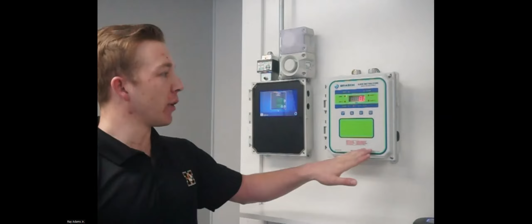Now, the reason that it's a NEMA 3R and not a NEMA 4X is that you do have those internal sensors in there. So there still does have to be air that moves in there in order for you to be able to detect the gas. Whereas our control panel, without any internal sensors, comes standard as a NEMA 4X enclosure. So the NEMA 4X has a steel welded plate across the front of here.